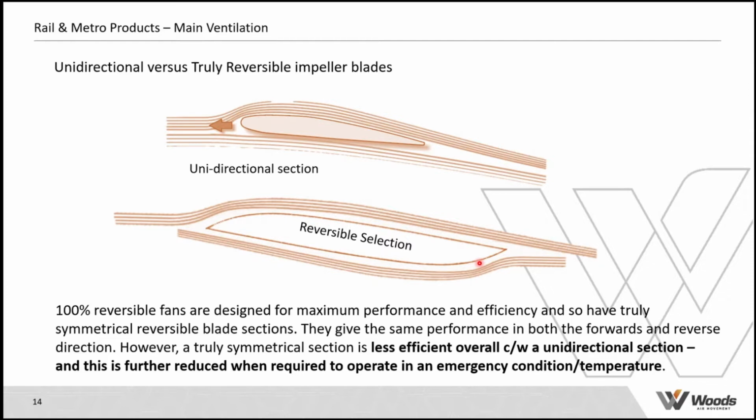Okay, so this kind of design of blade gives you 100% reversible performance. So you get the same flow, pressure, and efficiency in either direction. Okay, which is good. It's good for this application.